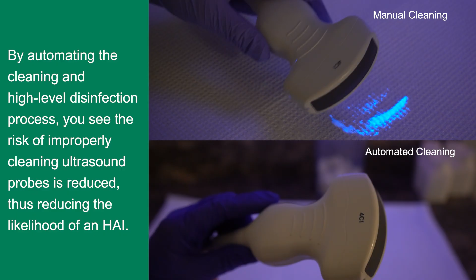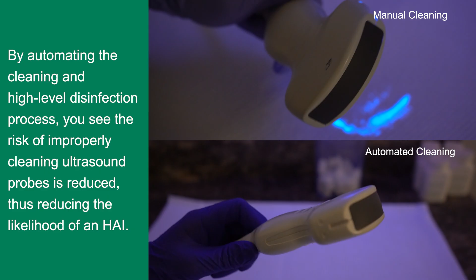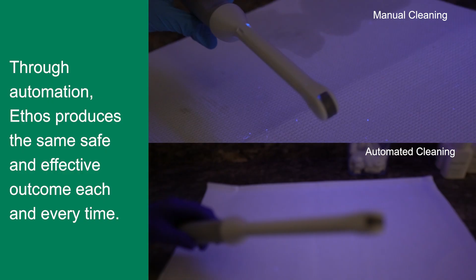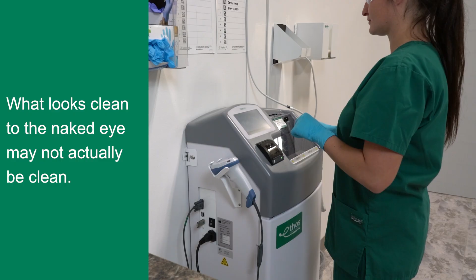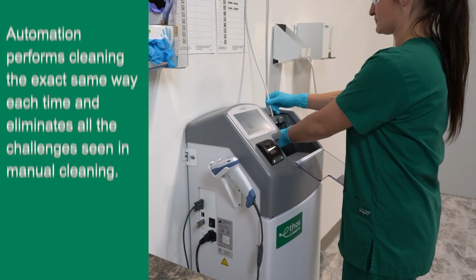By automating the cleaning and high-level disinfection process, you see the risk of improperly cleaning ultrasound probes is reduced, thus reducing the likelihood of an HAI. Through automation, Ethos produces the same safe and effective outcome each and every time. What looks clean to the naked eye may not actually be clean. Automation performs cleaning the exact same way each time and eliminates all the challenges seen in manual cleaning.